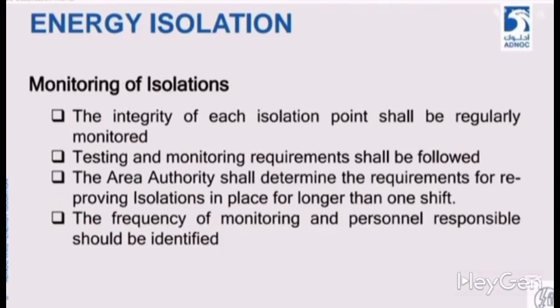Testing and monitoring requirements shall be followed. If we have some energy isolation where there is a high chance of leakage, we will ensure proper energy isolation by using drain valves, bleed valves, or gauges, or by mechanically, physically, or electrically operating equipment. The area authority shall determine the requirements for proving isolation in place for longer than one shift as per the area authority's recommendation. Isolation that lasts more than one shift will be verified and monitored.